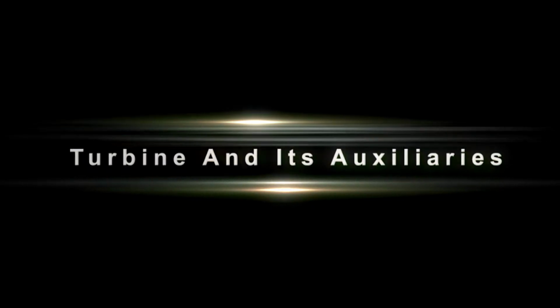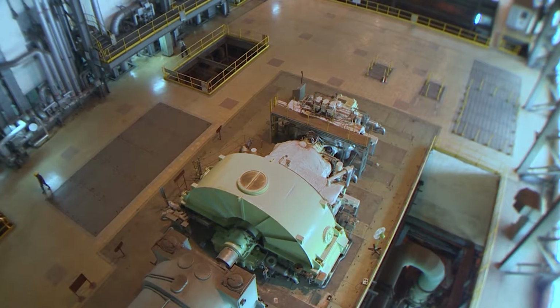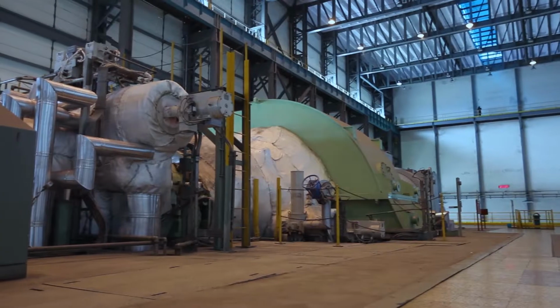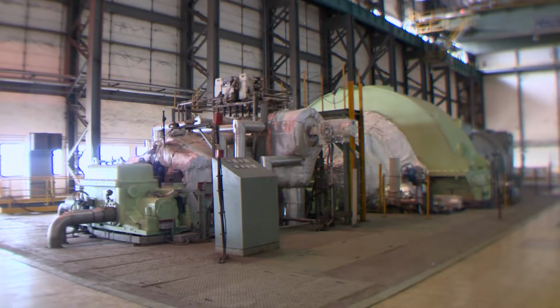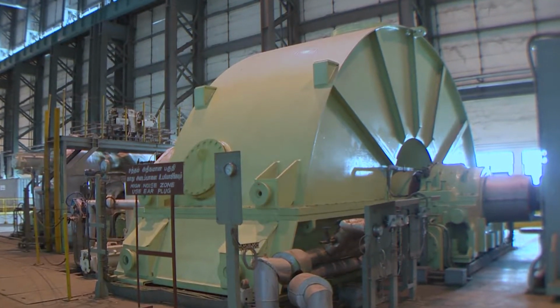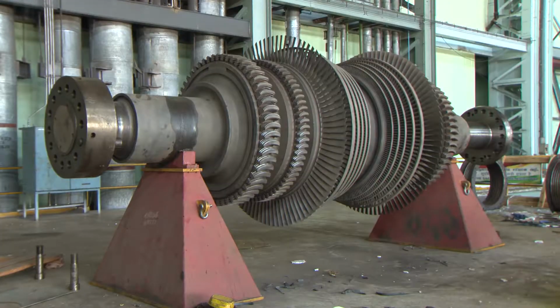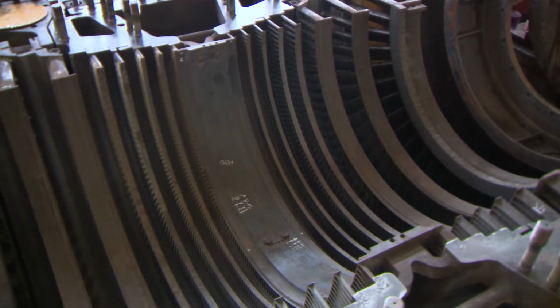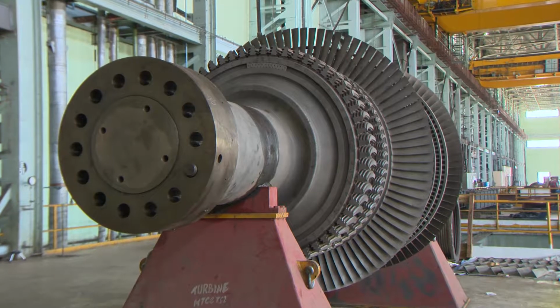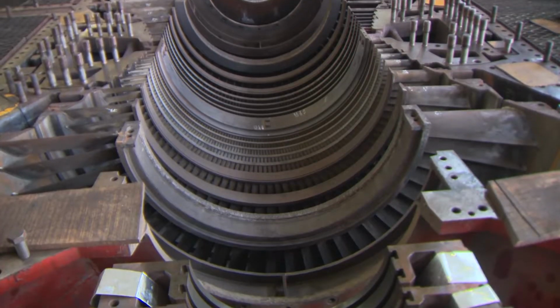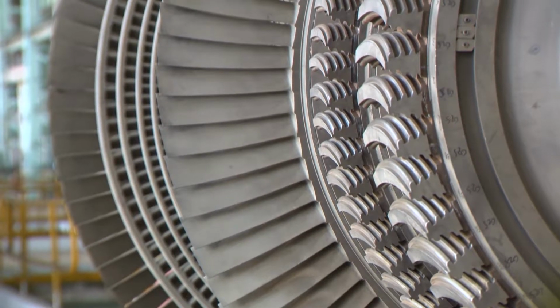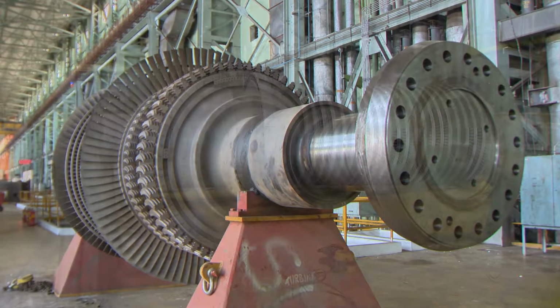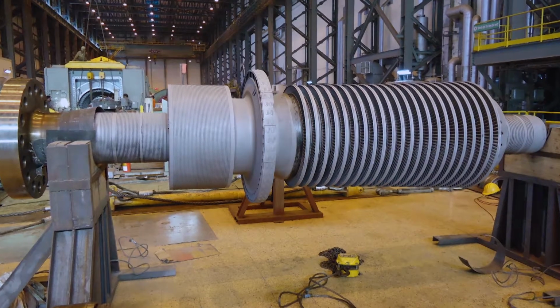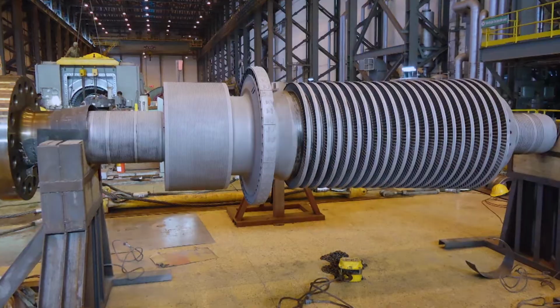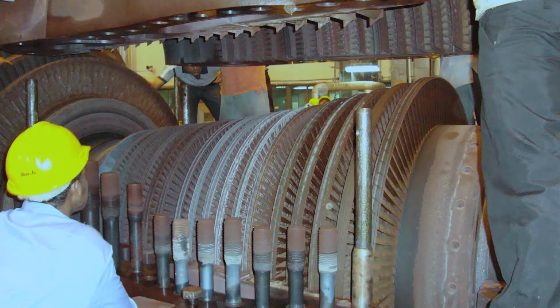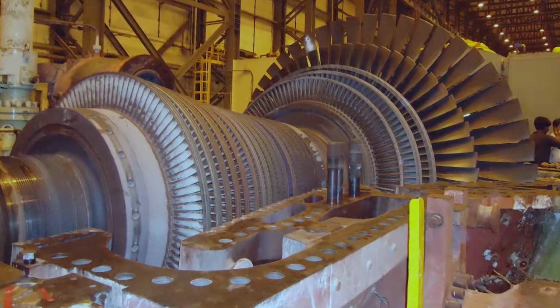Turbine and its auxiliaries. The turbine is a 3 cylinder, condensing, single reheat, regenerative, tandem compound reaction type. The turbine consists of casing and rotor. The blades assembled over the casing are called fixed blades, and the blades assembled on the rotor are called the moving blades. One fixed blade wheel and one moving blade wheel is called one stage. The HP cylinder consists of 1 impulse and 22 reaction stages. The IP cylinder consists of 17 reaction stages, and the LP cylinder consists of 5 reaction stages.